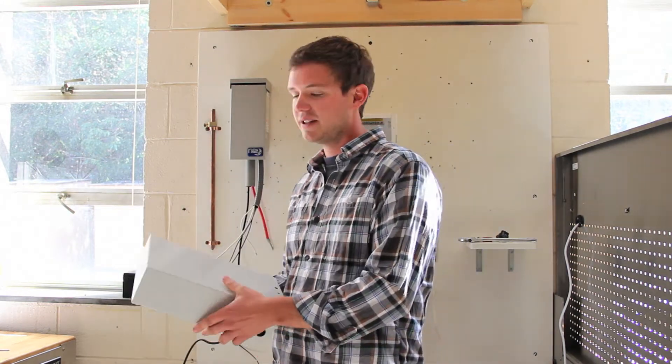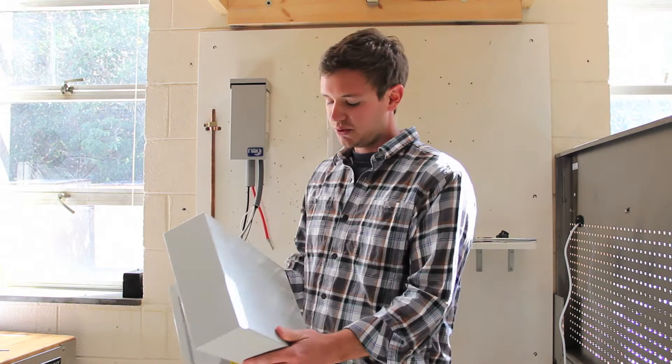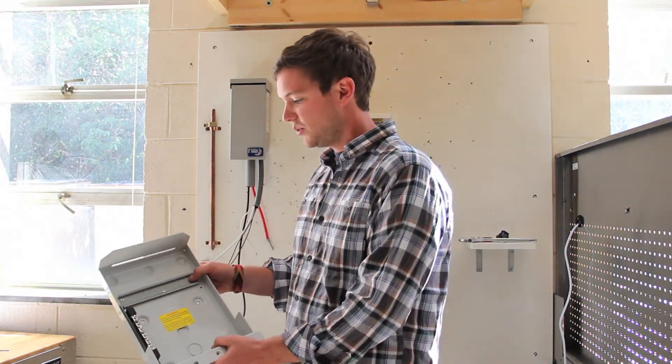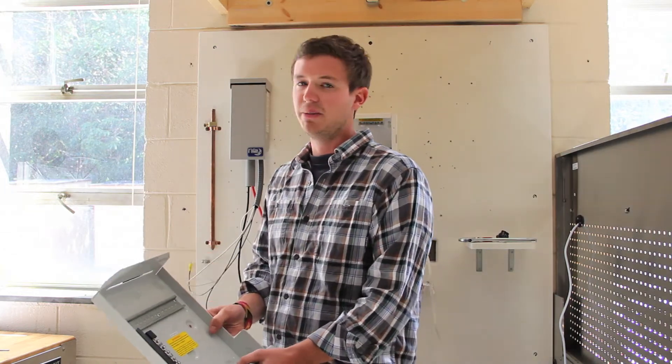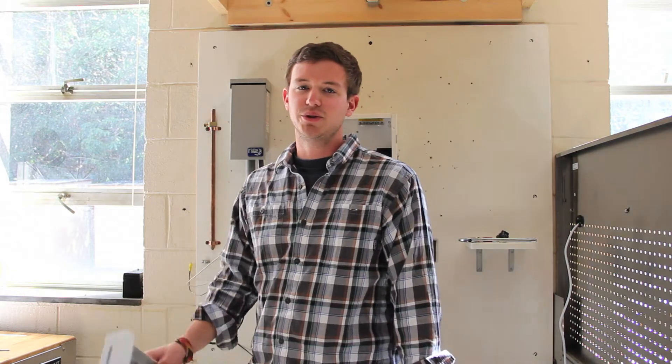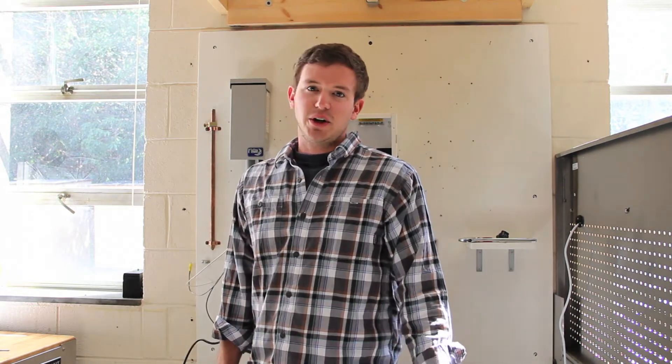Here's a larger combiner box that might be used in a commercial system. There's a spot for DIN rail mounted breakers or tip out fuse holders. Depending on your application, you might use a breaker for a lower voltage system. Most breakers are rated for either 125 volts DC or 150 volts DC.